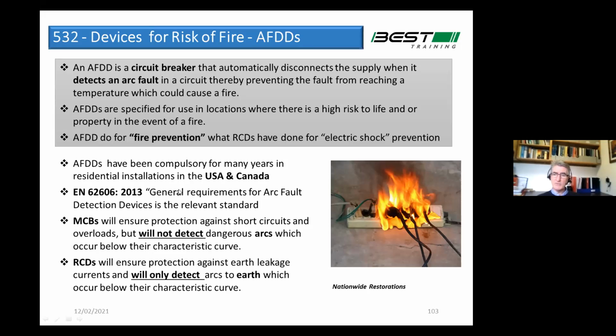I personally think we should be moving in the same way we stopped using screw-in fuses back in the late 70s, and we used MCBs, and then we started using ELCBs, and then we moved to RCBOs. Arc fault detection devices are going to do for fire prevention what earth leakage circuit breakers or RCDs did for protection against electric shock. Same thing, it's advancement in the technology. We should embrace it, and it's protecting lives, and let's go for it.